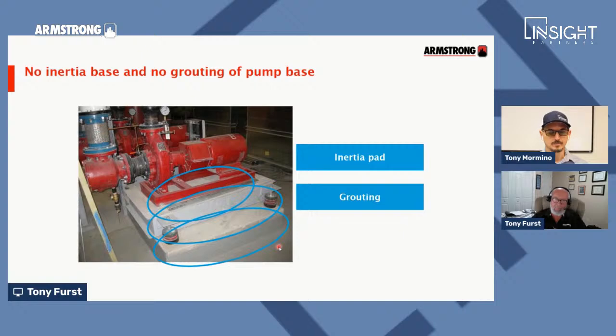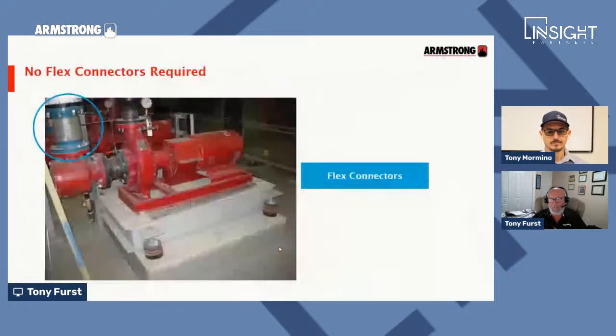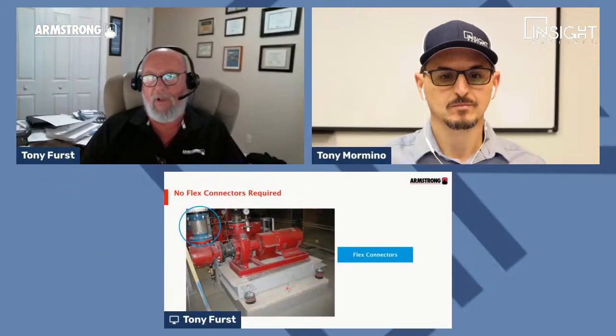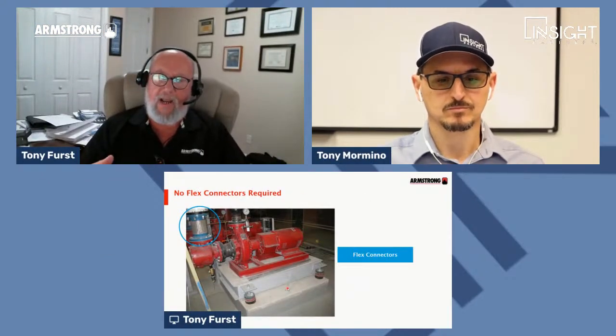Got it. So the next thing we want to talk about is flex connectors. These little flex connectors in the piping that everybody puts in are there because we've put all this stuff underneath the pump to isolate it from the piping system so it doesn't transmit noise and vibration. Well, because vertical inline pumps are inherently less prone to vibration, since they don't have an overhung load coming off the motor shaft - I'll show you in the next picture what I mean - when we get rid of that overhung load, we get rid of so much of the vibration.